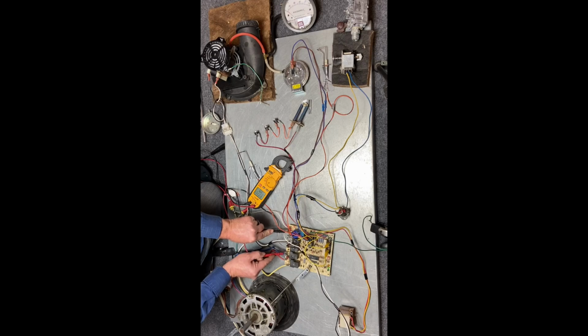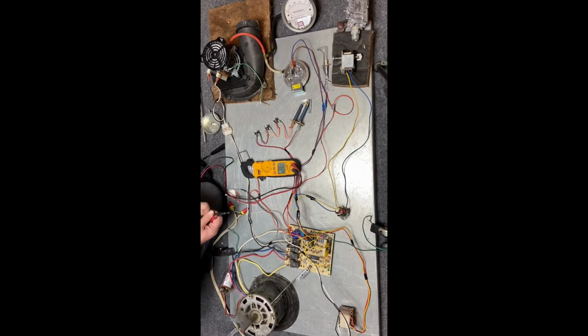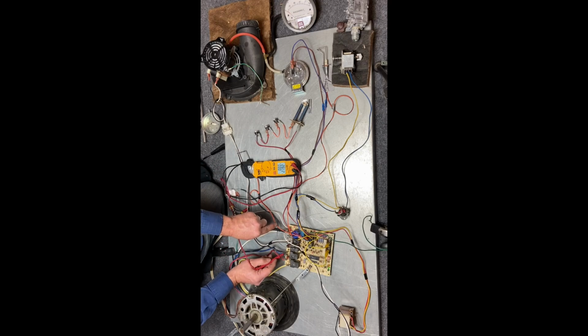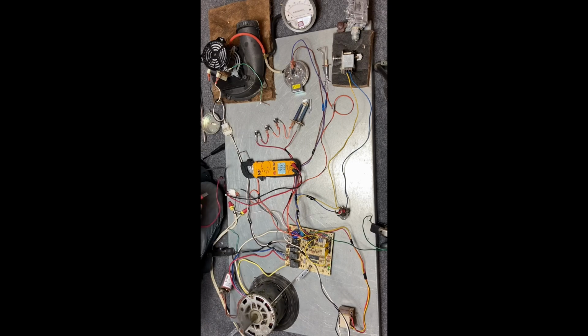So between common, or high speed, and neutral, I'm showing 121 volts. And if I check between neutral and high speed, I'm showing 121 volts. Also between heating, medium low, 138 volts. And between fan, I get 178 volts. And between unused, 156 volts. If you see, the voltage actually increased because these unused windings are actually generating electricity and it's reading back EMF. But there's no place for it to go because the switches, these relays, are open.